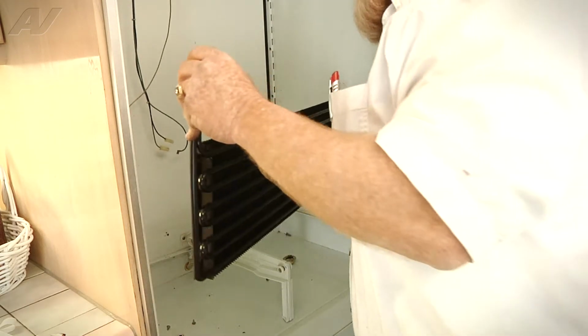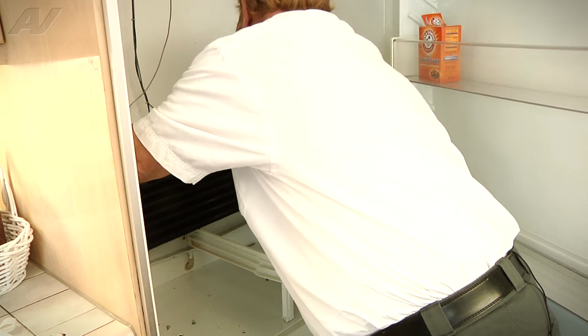Now we will loosely place the evaporator in the spot where it's going to go. So now what we need to do is snake the heat exchanger back into place and get that little cap tube up over the freezer piping. Then we'll guide it down into the hole that goes through the floor of the machine compartment and ceiling of the refrigerator. Once that cap tube is gone through, it will start to move a lot easier.